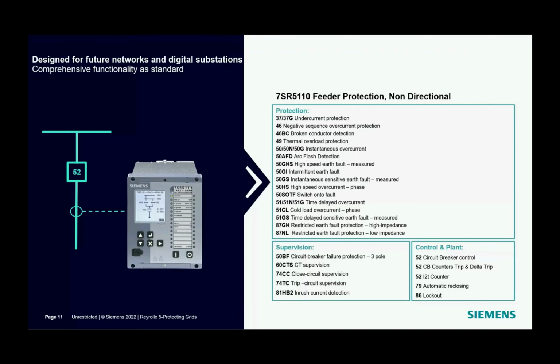The Reyrolle 5.1.10 devices provide primary function of overcurrent and earth fault protection functionality for medium voltage substations, as well as backup protection for other protection devices. For example, it may be in a line feeder, transformer, generator, motor, or busbar protection system, supporting the main protection, while you can keep 7SR5.1.10 as the backup feeder protection. The 4CT input is suitable for connection to both 1 amp and 5 amp current transformer secondary windings.